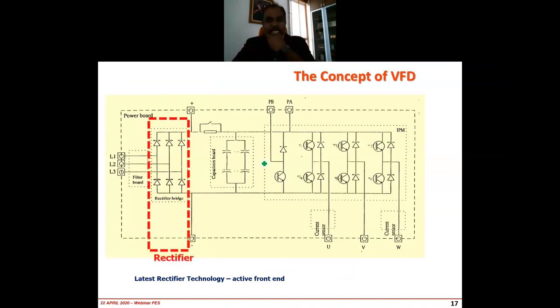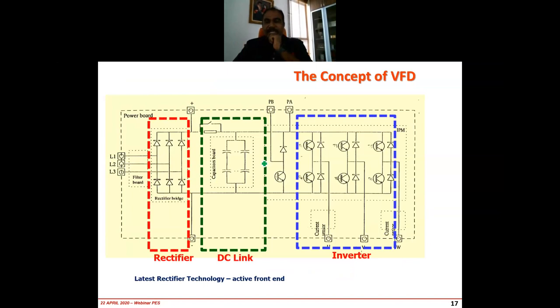VFD, I won't go into details on this, because as you know, the typical variable frequency drive is completely a power converter. It comprises a rectifier as well as an inverter as major components. Obviously, there are a lot of other issues. The reason I show you these slides is that I will conclude in the last slides that you have to understand one thing. If you think that a variable speed drive is not going to give you savings, please don't install a variable frequency drive, because there is going to be a lot of maintenance cost that comes in when you install one.